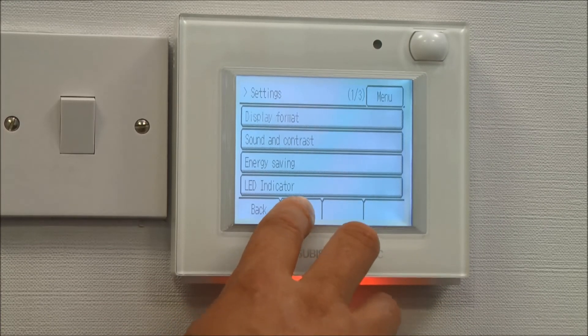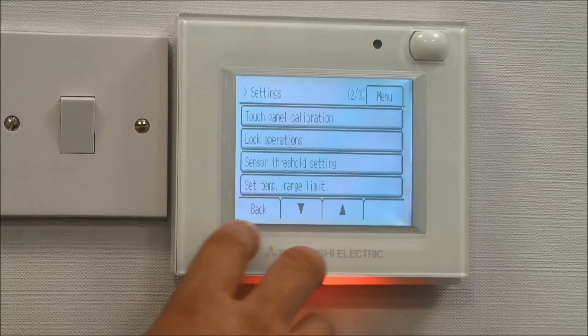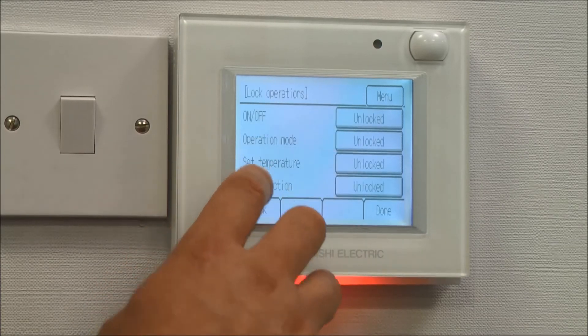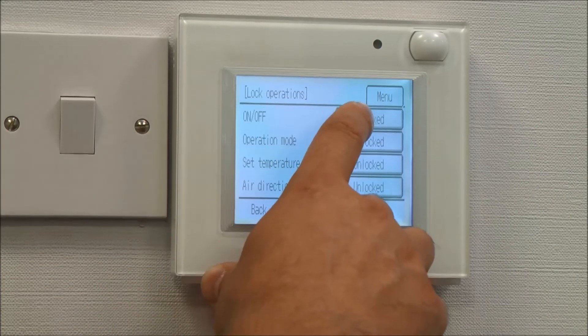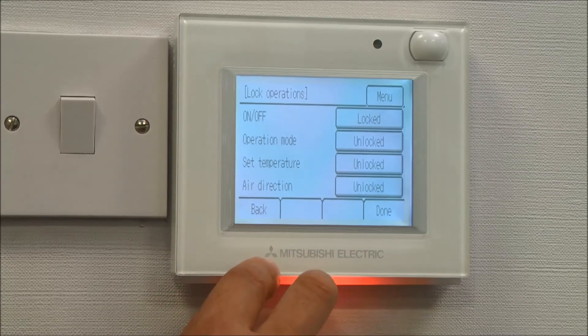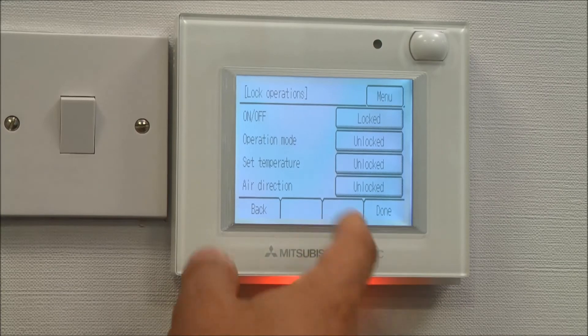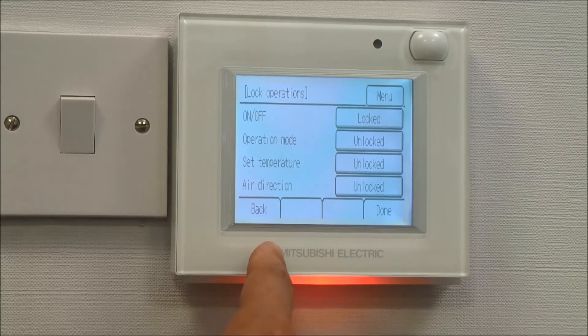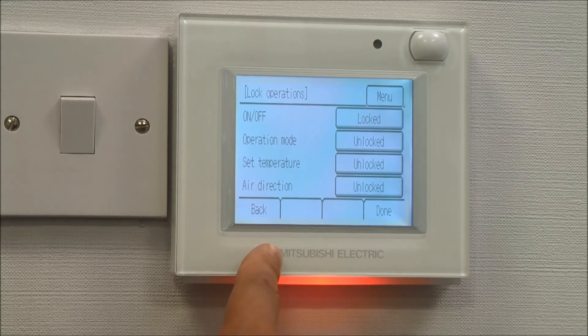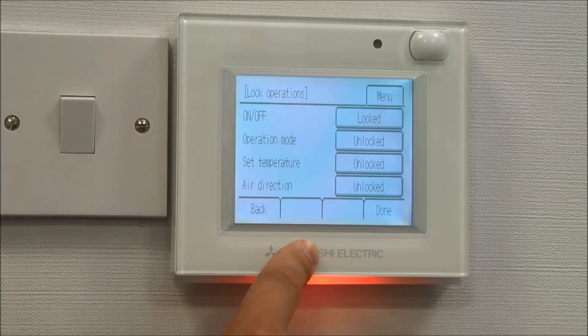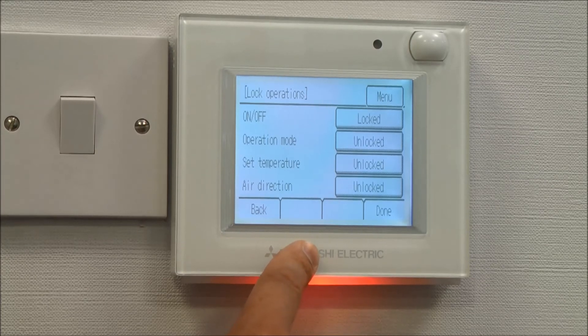One other thing we need to do is scroll down to lock operation, and we need to lock the on-off button. The reason we're doing this is we're making the PIR sensor make the decision about when the air conditioning unit is on or off. Therefore, we need to prohibit operation of the on-off button.